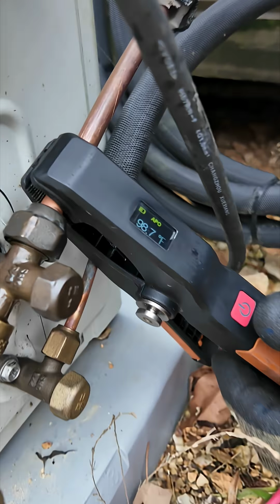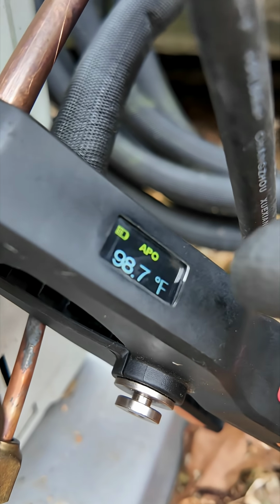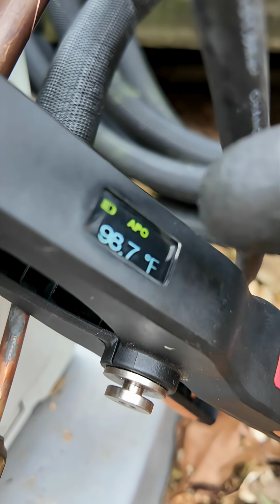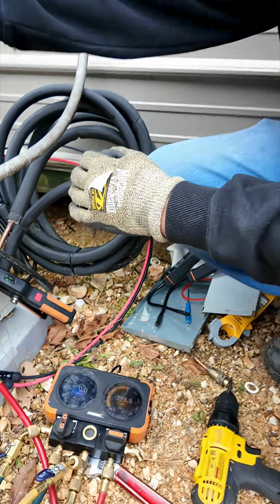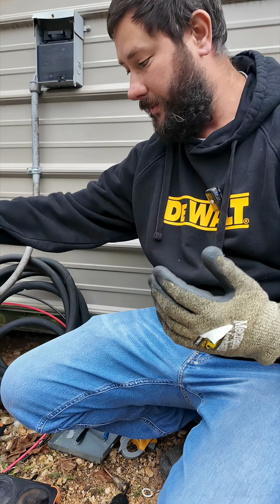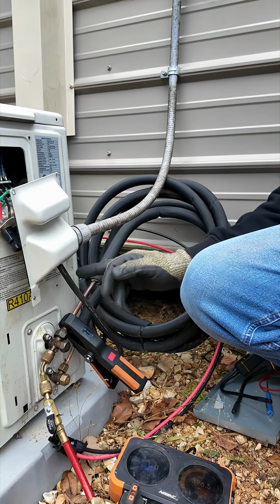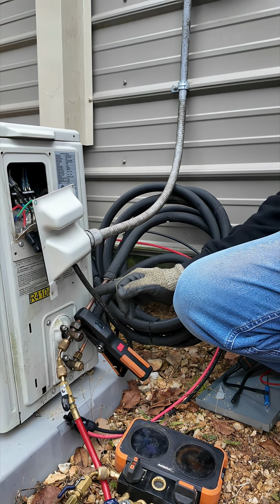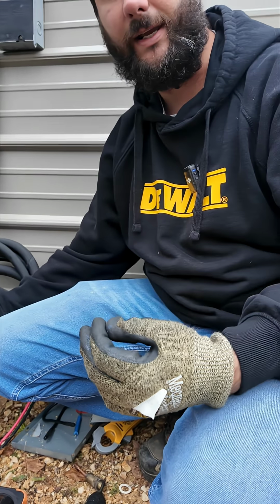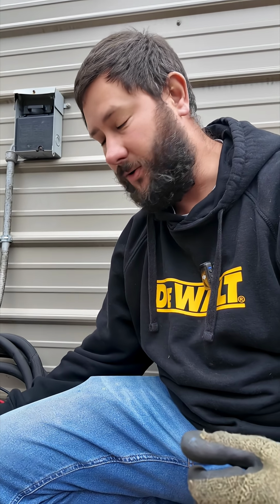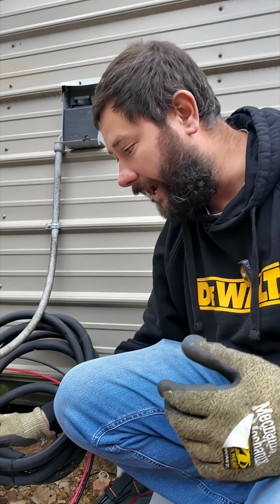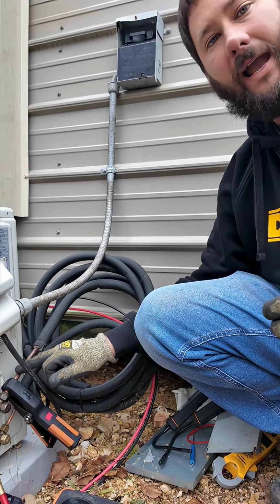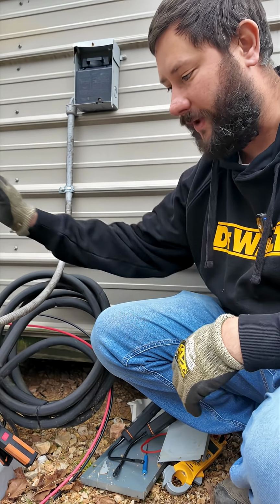Here's our temperature probe. We're measuring the hot gas line. It's 98.9, so it's almost 100 degrees right now. During the cooling mode, this is carrying a low pressure vapor, so we may have pressures at 100 psig, but in heating, it's going to be over 300 psig. And during heating, we're carrying a hot gas. We're carrying a high pressure, high temperature vapor.